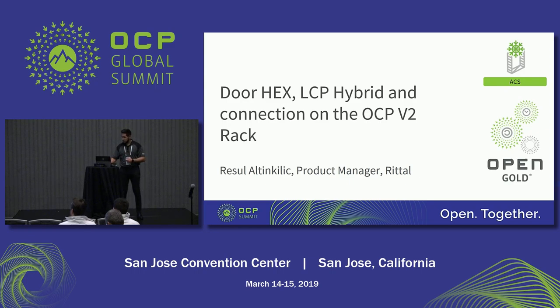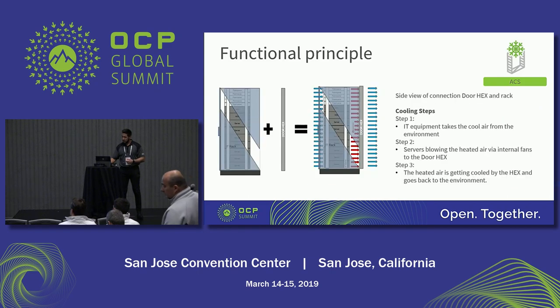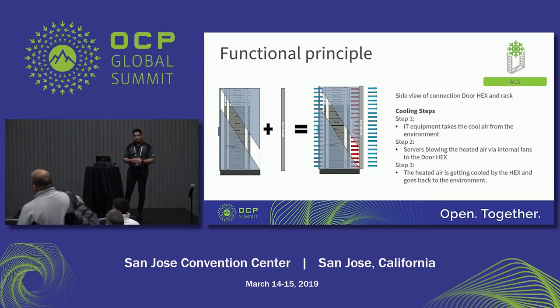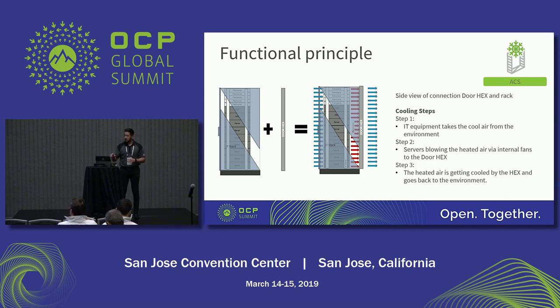My colleague John already told you about the technical stuff, and I would like to tell you about the functional principle. As you know, the door heat exchanger is not rocket science. I will show you the side view of the rear door heat exchanger. On the left, you can see the standard IT rack with some servers and storage inside. If you combine it, you get the result like we have it there.